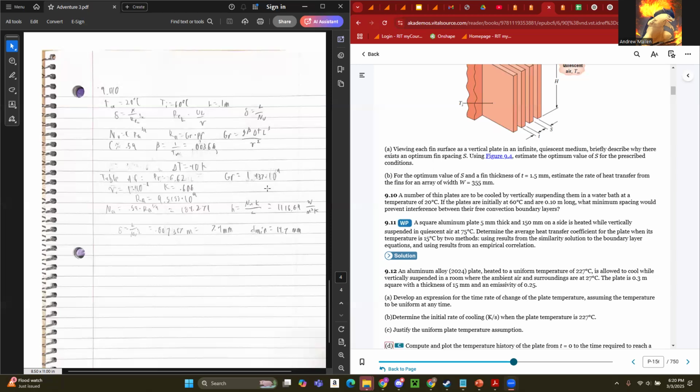So plugging the length and the Nusselt number into the boundary layer distance equation gives us a distance of 0.007367 meters or 7.4 millimeters. Since there are multiple plates, we have to be mindful of the fact that this is the distance from the layer to one of the plates. So in fact, we need a minimum distance of 14.7 millimeters in order to account for the fact that there's a gap between plates.